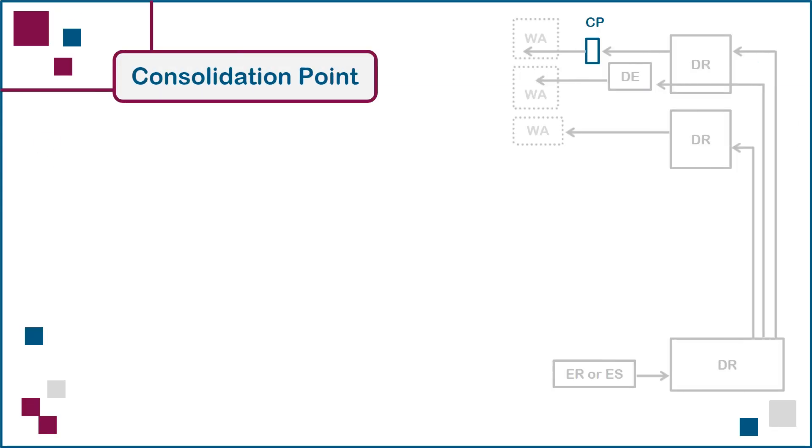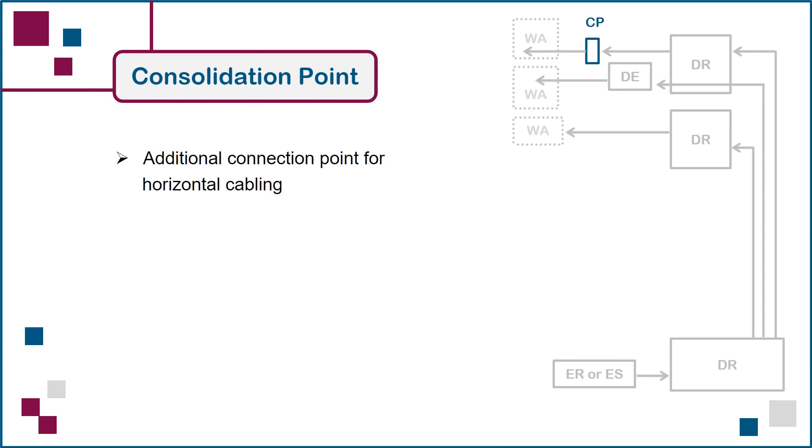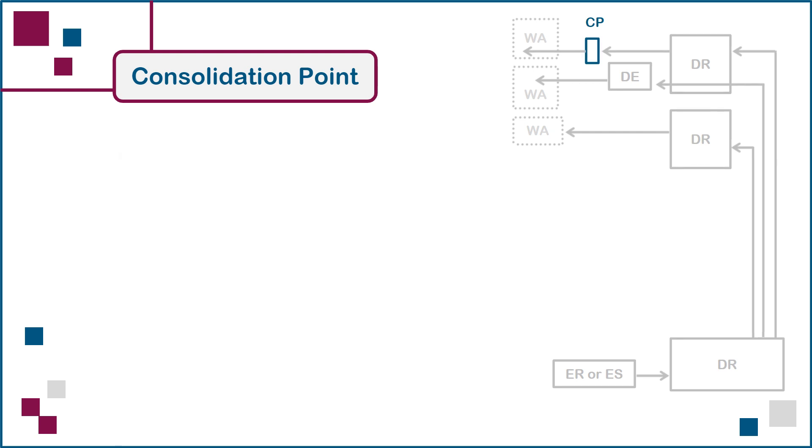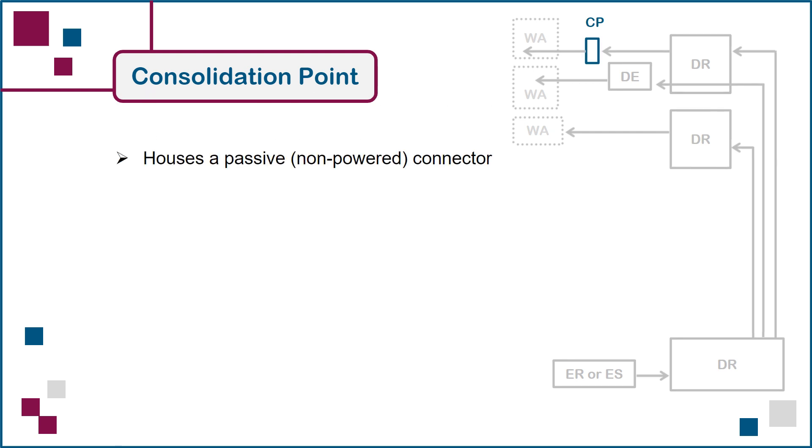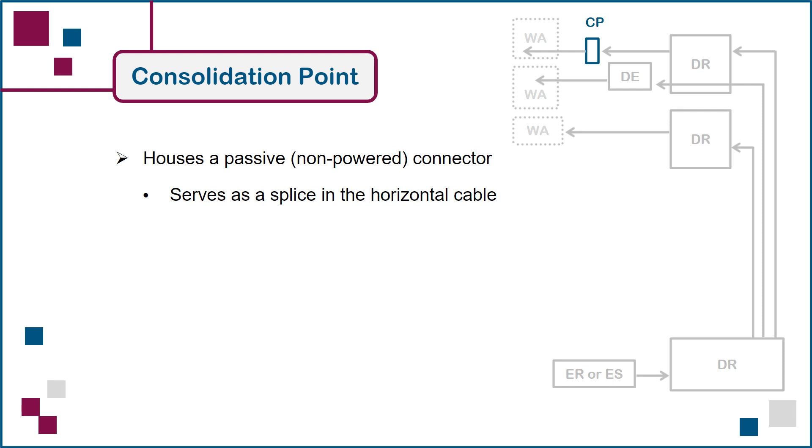Next, we have the consolidation point space, which serves as an additional connection point for horizontal cabling. The consolidation point houses a passive or non-powered connector that essentially serves as a splice in the horizontal cable. It allows for the partial rather than end-to-end replacement of the cabling run in cases where only a segment of the cable needs to be replaced.